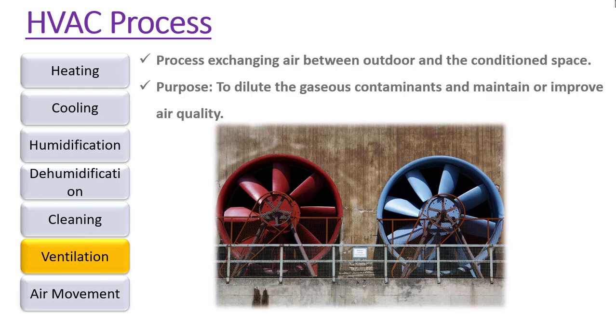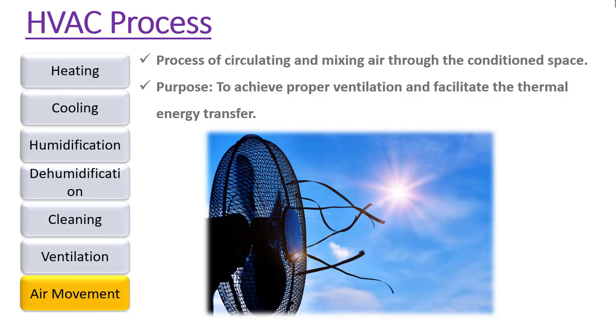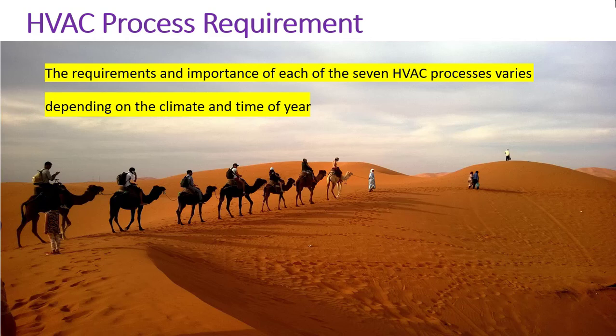Ventilation is the process of exchanging air between the outdoor and the conditioned space; its purpose is to dilute gaseous contaminants and maintain or improve air quality. Air movement is the process of circulating and mixing air through the conditioned space; its purpose is to achieve proper ventilation and facilitate thermal energy transfer. The requirement and importance of each of the seven HVAC processes varies depending on the climate and time of year. For example, dry deserts may not need dehumidification, hot climates may not need heating, and areas near the sea may not need humidification.